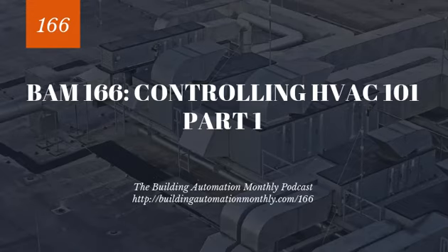So you've got these VAV systems, and as I mentioned, they can be variable, but they can also be CAV, which is constant air volume. This tends to be on units where you're providing constant air volume. With a constant air volume system, you're often modulating the temperature control and resetting the discharge temperature based on average space temp. So maybe it's serving multiple spaces, and you've got these constant air volume boxes that are balanced to a certain CFM.